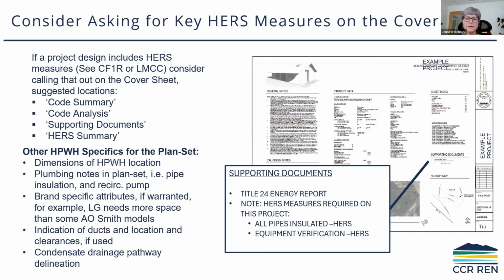And then that condensate, you're either going to send it to one of the sinks above the P-trap or a floor drain that's part of your whole house's drainage system where you're not going to get freezing and proper termination for that. Or, same like how you deal with your washing machine in cold climates. So you wouldn't just send it outdoors where the end of it could freeze. And when we talk freezing climates, which is funny because it's also applicable to just places that have cold nights.